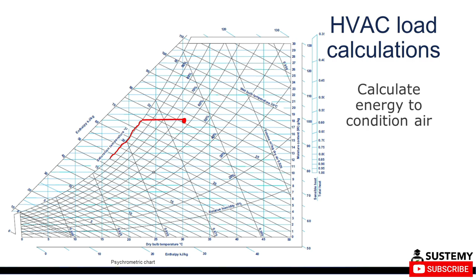If you know, for example, the temperature and relative humidity of air supplied to an HVAC system, the leaving temperature and humidity, so let's say it's going into a heating or cooling coil, and the air flow rate, you can then use the psychrometric chart to identify the amount of energy that has been transferred to the air.